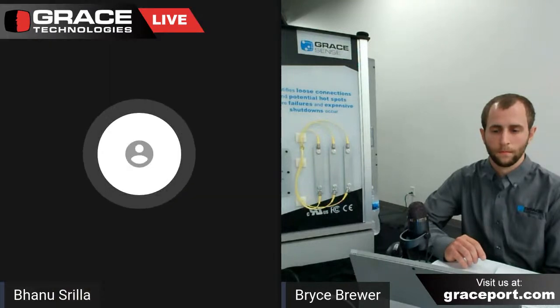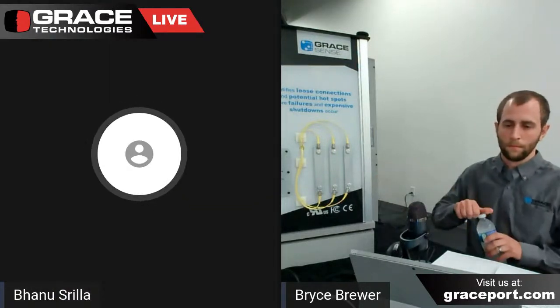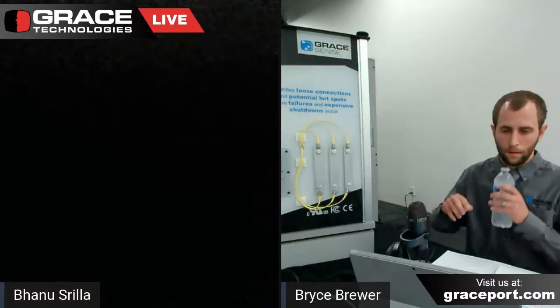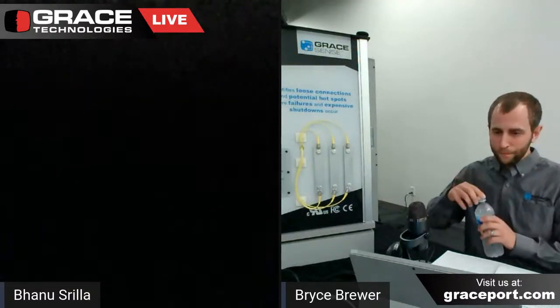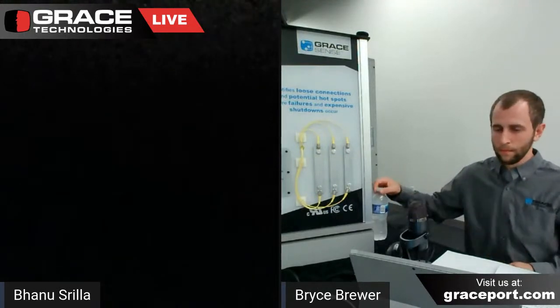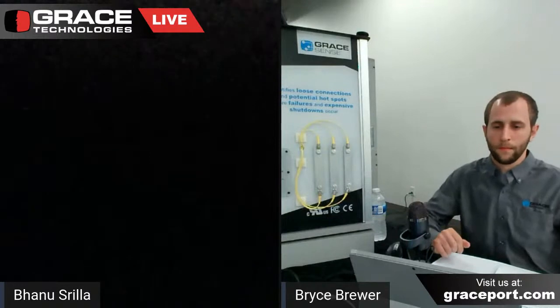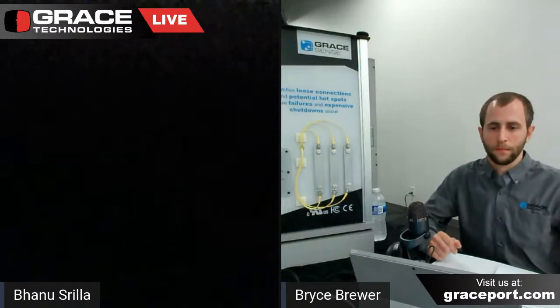If you don't have manufacturer guidelines, for example equipment that's 30 or 40 years old with no manufacturer available for it, what you would do is use the NFPA 70B standard, or ANSI NETA MTS maintenance and test specifications. These are the standards you would use in that case. So primarily you focus on manufacturer recommended guidelines per the manufacturer on record, and if not, then you go to those standards.